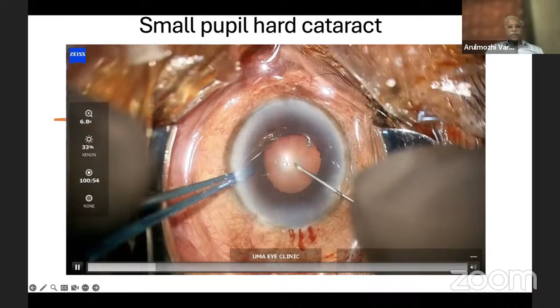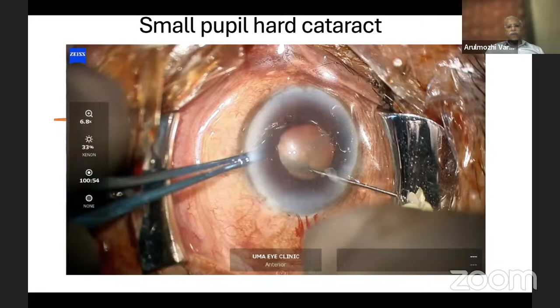Remember, if you watch carefully, you would find that there is literally no wound leak at all at the main wound or at the side port. This is critical. This is something that I want all of you to learn, that the wound sizing should be precise. It should be appropriate to the tip and the sleeve that you're using. That is why it's so critical that you use standard phaco tips and standard sleeves. Don't mix and match. Don't scrimp and try to save on those issues. They are very critical. Do not change them.